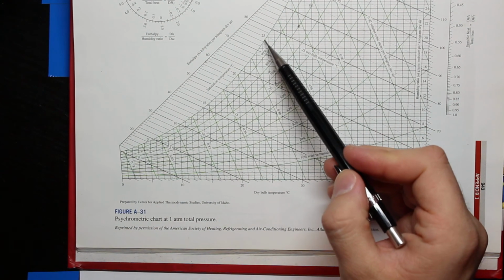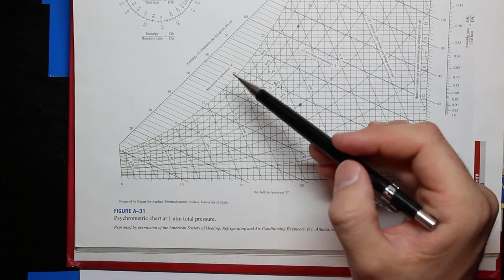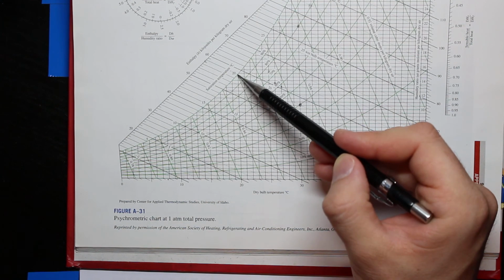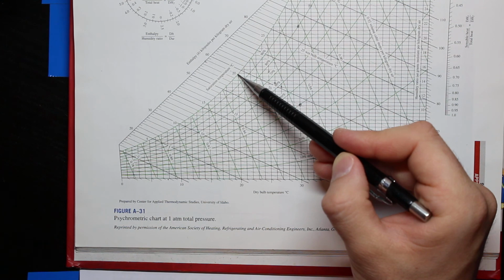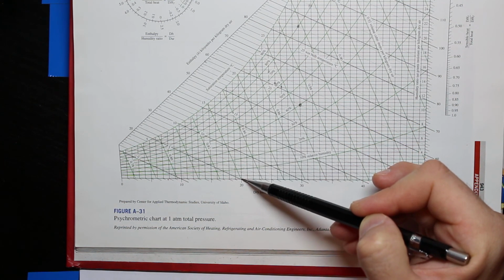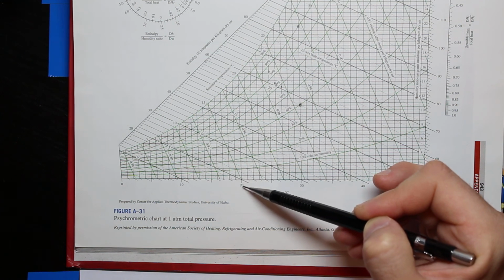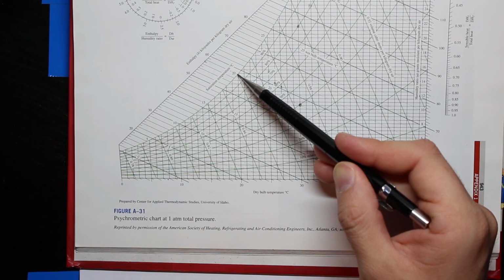As I said, this green line is for relative humidity equal to 100%. Let's focus on a temperature of 20 degrees C, which is right at this point. If I want to find the dry bulb temperature, I need to go vertically down, and that is my dry bulb temperature. You see it says 20 degrees C. So for the dew point temperature, the dry bulb temperature is also 20 degrees C. The other one that I want to read is the wet bulb temperature.